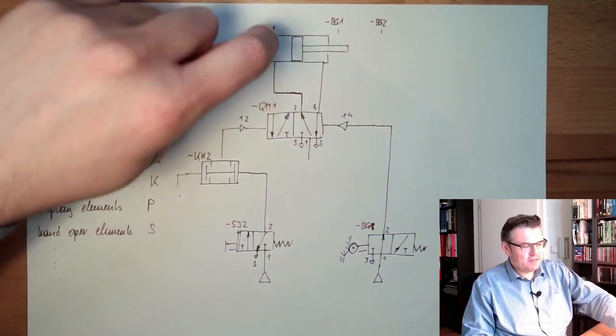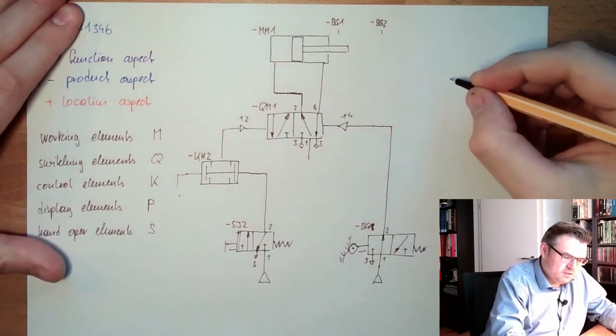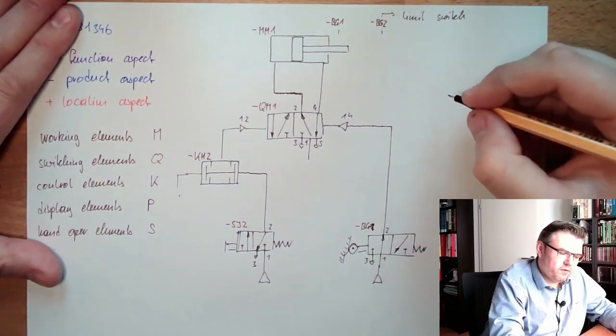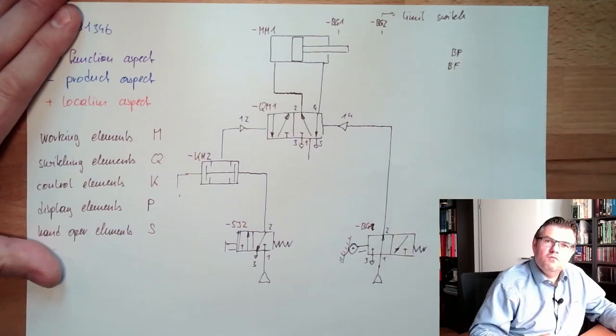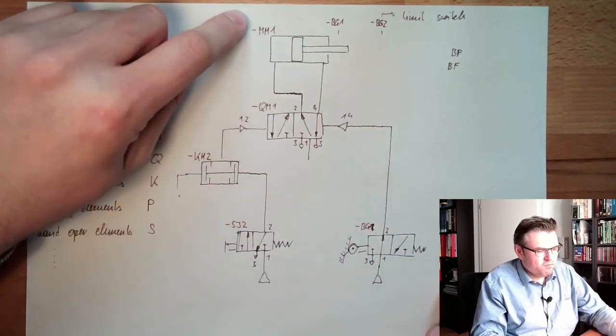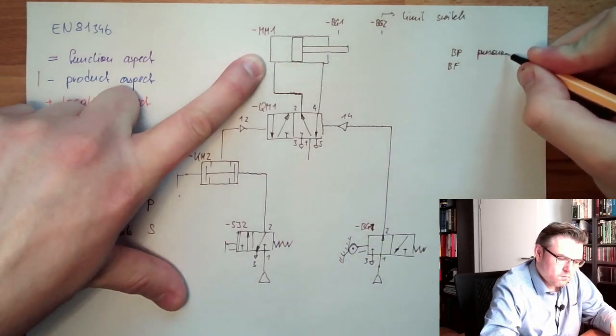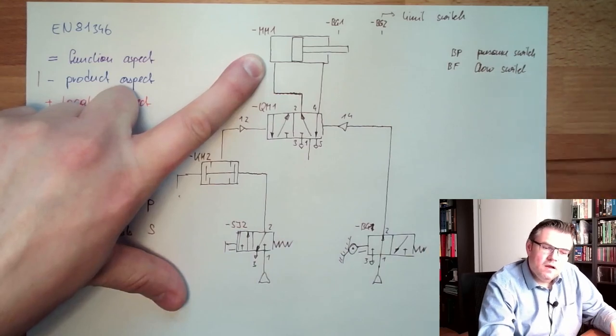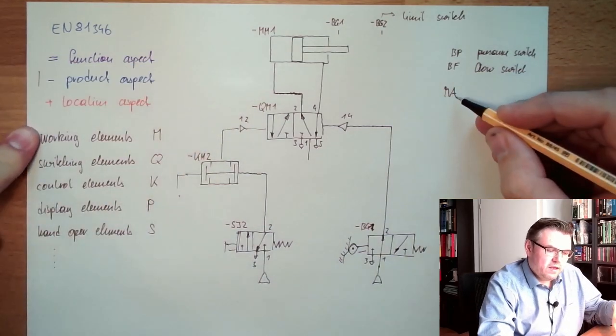Now what is the second letter? The second letter shows a little bit further what it is. For instance, this BG here is a limit switch, second G limit switch. There would also be for instance BP, that's a pressure switch, or there would be BF, a flow switch. So the second letter shows a little bit more in details. For instance here MM, that's a hydraulic cylinder. MA, electrical motor.